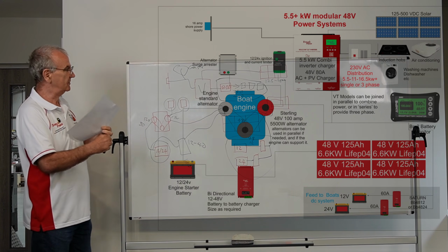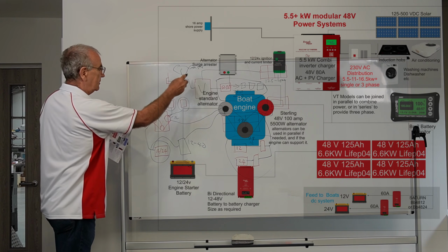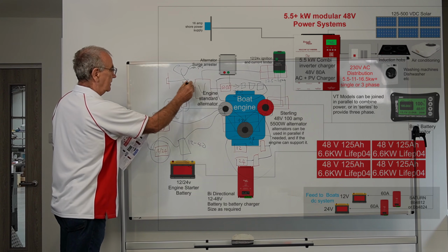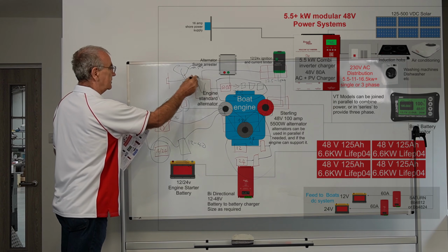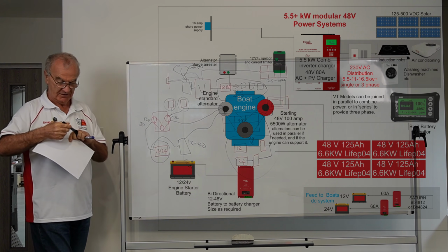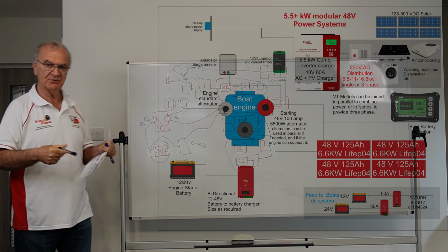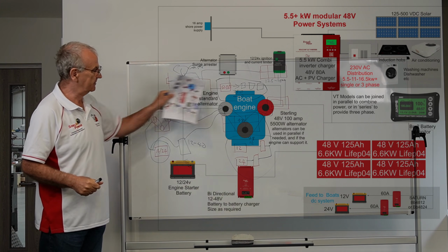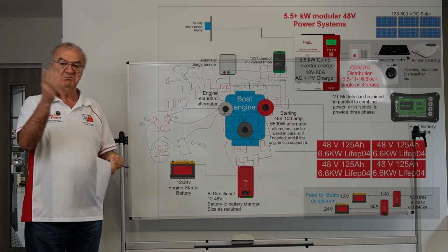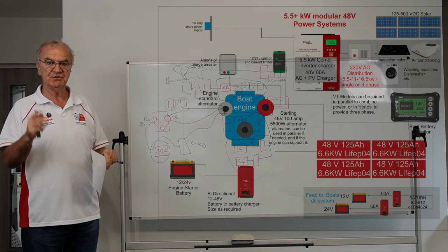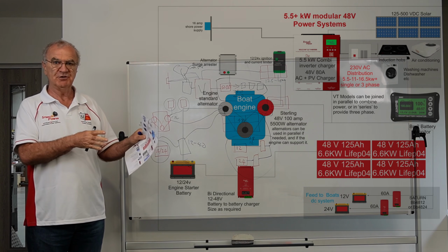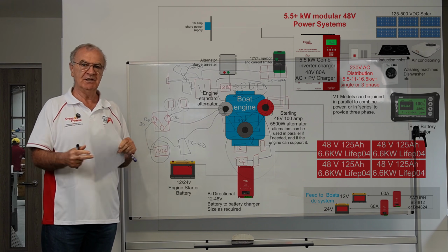You might have a situation where you put 2 Vulcans on and both come on when the genset's running, but only one comes on when you're running from shore power. So when the genset's running, you want to load it up, charge this battery bank as quickly as possible. Put 2 of them on, but when you're on shore power, the limitation of the shore power simply won't let you use 2 of them.